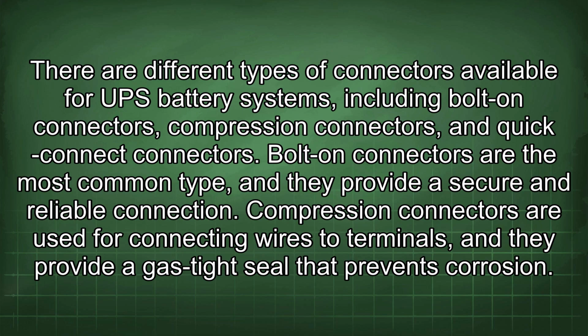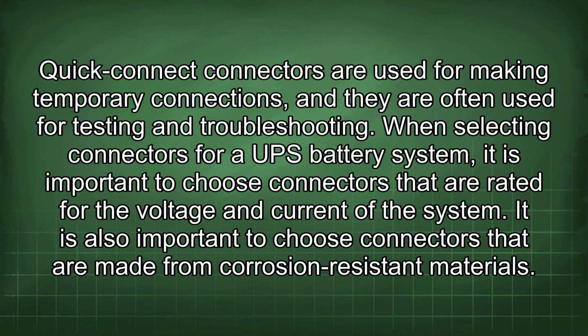Bolt-on connectors are the most common type, and they provide a secure and reliable connection. Compression connectors are used for connecting wires to terminals, and they provide a gas-tight seal that prevents corrosion. Quick connect connectors are used for making temporary connections, and they are often used for testing and troubleshooting. When selecting connectors for a UPS battery system, it is important to choose connectors that are rated for the voltage and current of the system. It is also important to choose connectors that are made from corrosion-resistant materials.